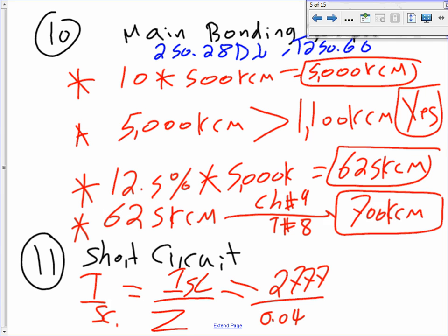I know we didn't do it on the first one, and I would like you guys to do it on this one. It's really nothing, it's one formula. You take the line and just divide it by the impedance. You're absolutely right, we didn't do it on the first one. So if you do this, that will get you 69.4 kiloamp.